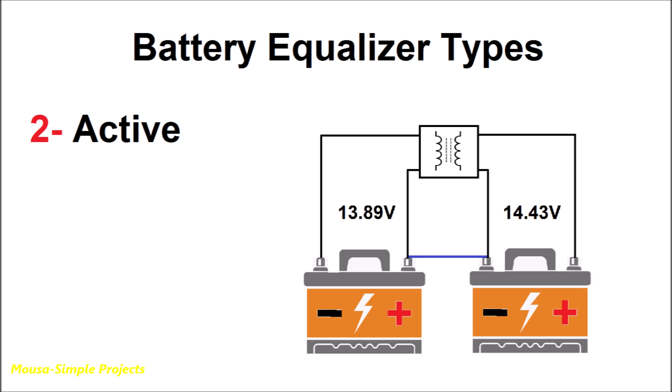The second type is called active battery equalizer. In this method the battery equalizer uses the excessive energy that is stored in the battery with higher voltage to charge the other battery that has lower voltage. So the active battery equalizer has higher efficiency than the passive type, but it is expensive and its circuitry is complicated.